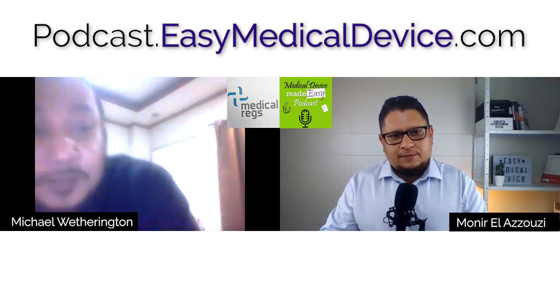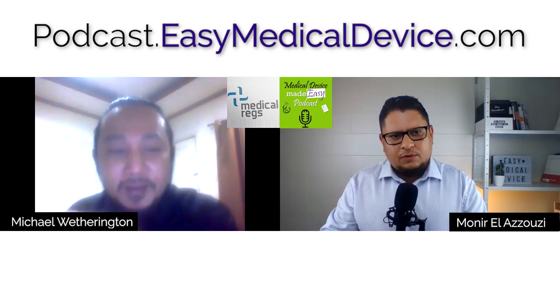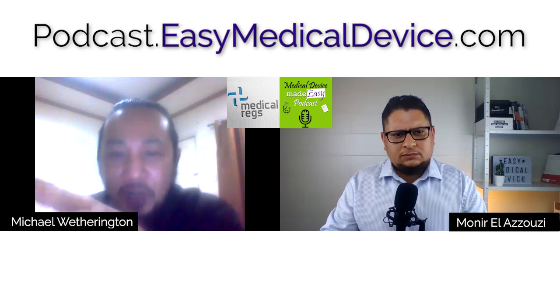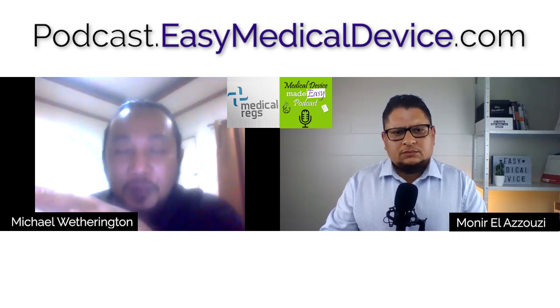Remember, I mentioned earlier that in order for you to have a higher success rate to obtain your product safety certification for your device, during your product design and development, try to do some of this testing as much as possible. It will let you know if you need to make adjustments, like if a leakage current test exceeds the limit, at least you can still tweak it before submitting for formal certification.